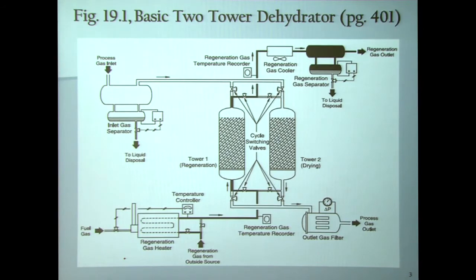The gas initially comes into a separator followed by an inlet filter coalescer or filter separator. This is probably the most important part of the entire unit, because you really do need to have excellent separation of the liquids and mist from the vapor.